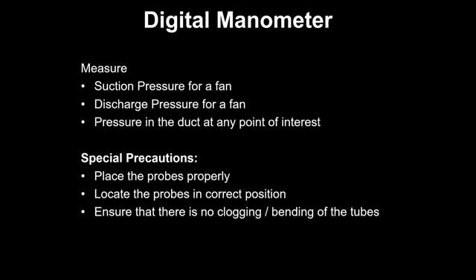Now there are cases where even a damper, if it is stuck internally, can have a pressure drop. We have seen a pressure drop across the damper as high as 100 mm water column, which was 10% of the fan power, because the total fan was developing 1000 mm and 100 mm was lost in a damper because it had got stuck. From outside it was looking as if it is open, but it was stuck internally, and that connection was damaged or broken, and it was having 100 mm. So along the duct also we need to do measurement. For that, digital manometer is used.